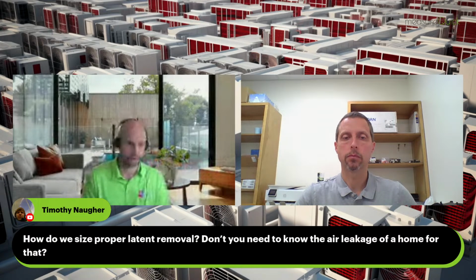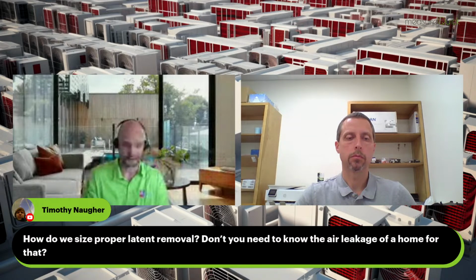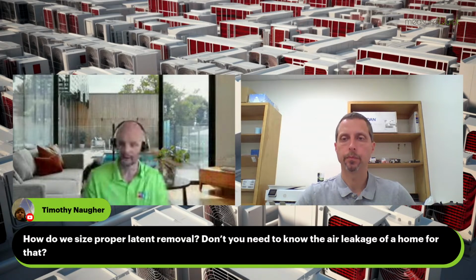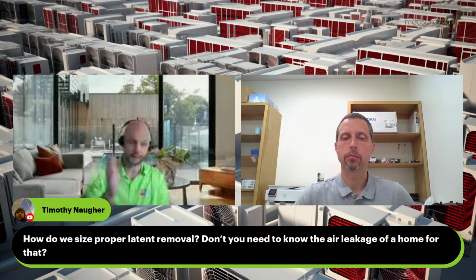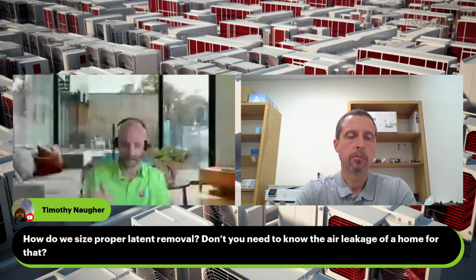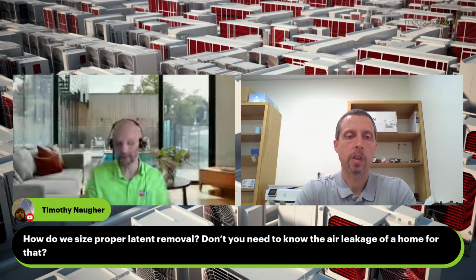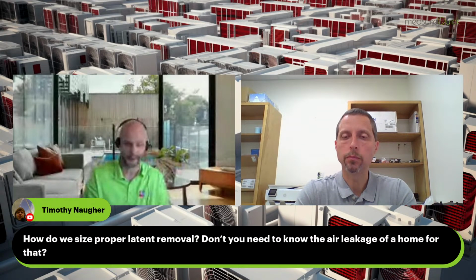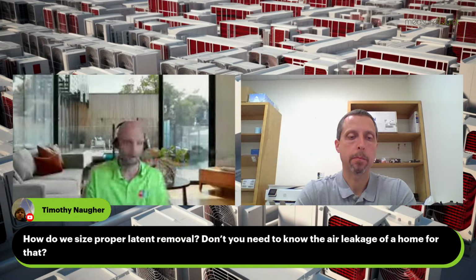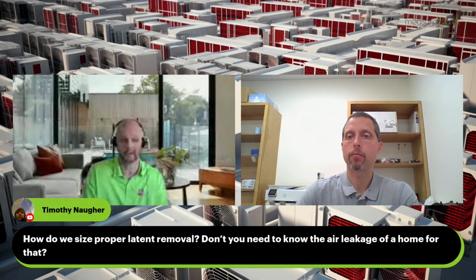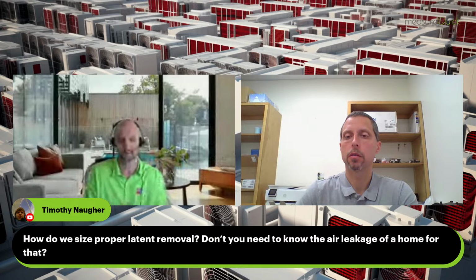And so we have a chart that we use internally. We know if it has exterior rigid insulation, there's a range of ACH that house is probably going to test in. We know if it's not using exterior rigid, there's a range of ACH the house is probably going to test in, and we stick pretty religiously to designing to those numbers. For instance, exterior rigid insulation, we know it's going to test between 1 to 3 air changes. So we use 3, and if we know the builders really well, we'll use something even more dialed in, like 2.5 or 1.5, depending on what they test at.